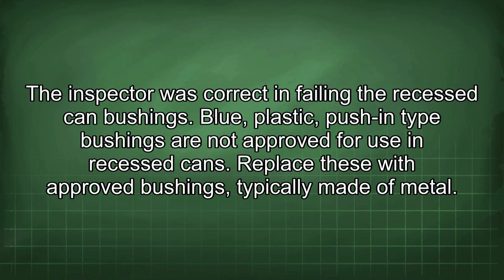The inspector was correct in failing the recessed can bushings. Blue plastic push-in type bushings are not approved for use in recessed cans. Replace these with approved bushings typically made of metal.